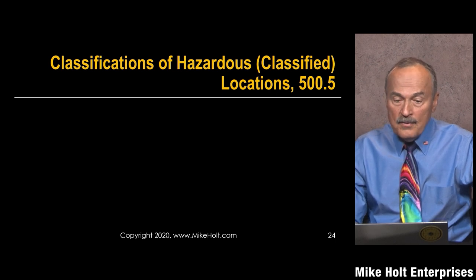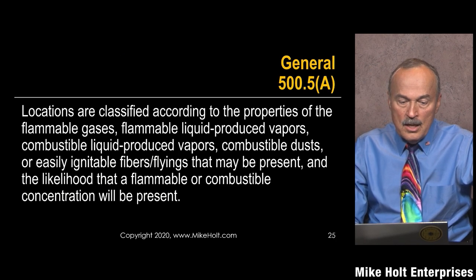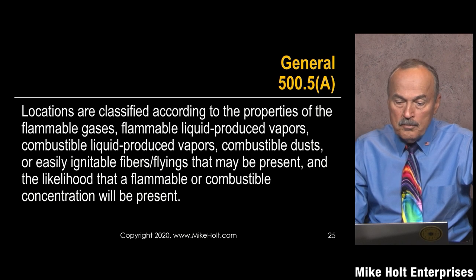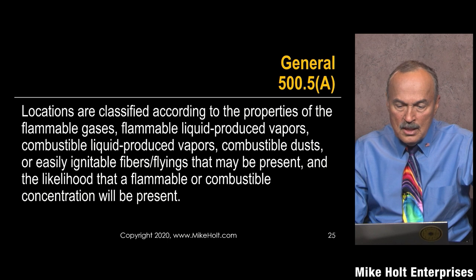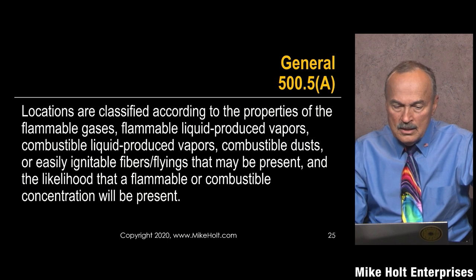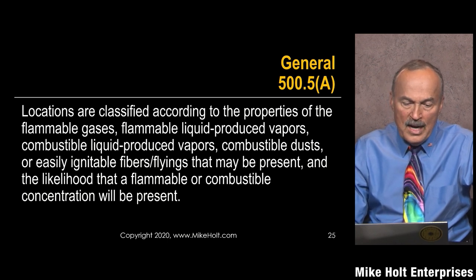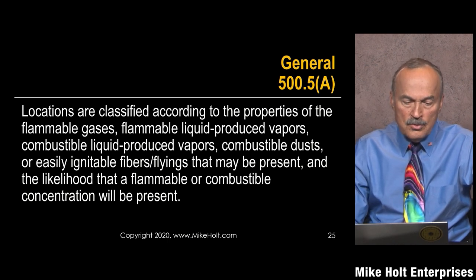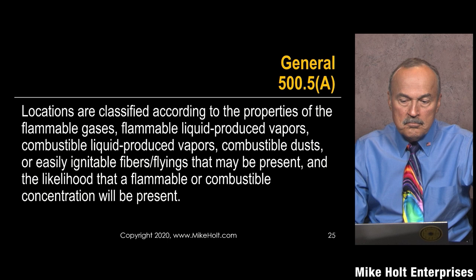Now we're going to be classifying locations. The locations are classified according to the properties of the gas — flammable gas, flammable liquid-produced vapors, combustible liquid vapors, combustible dust, easily ignitable fiber or flyings that may be present, and the likelihood that a flammable or combustible concentration will be present.